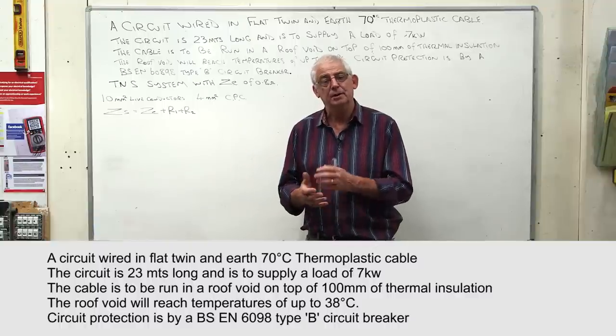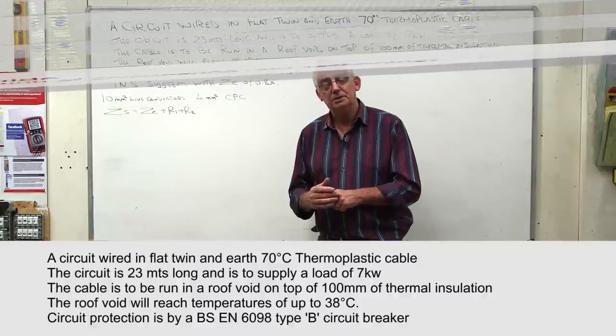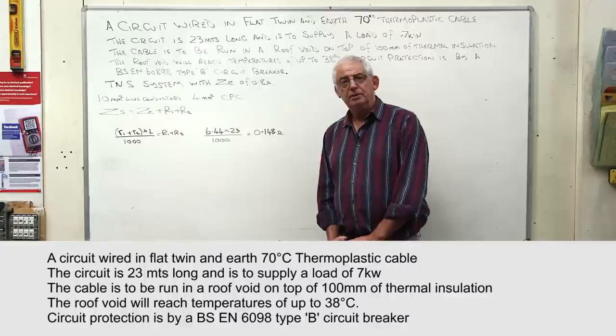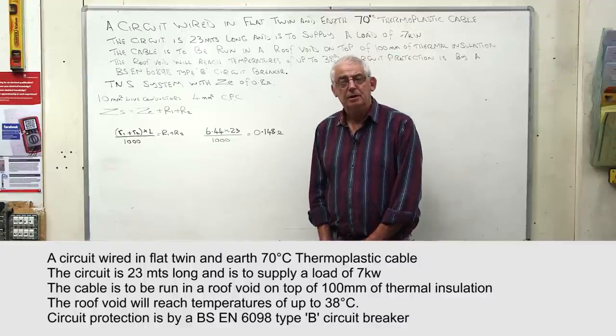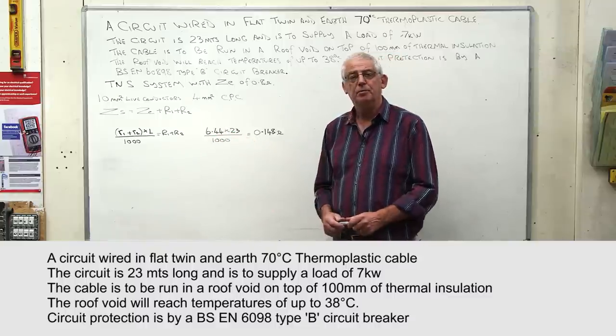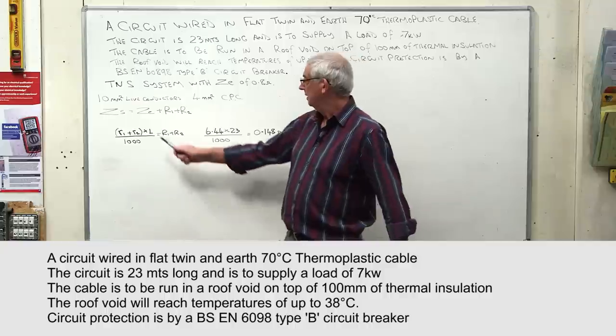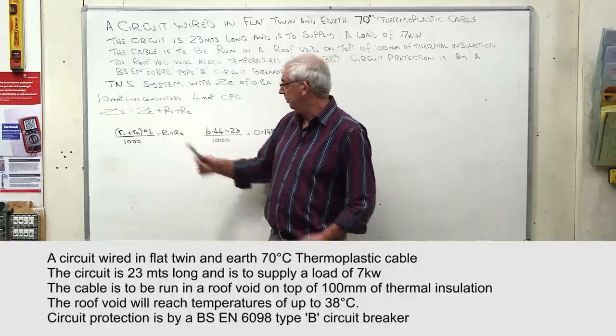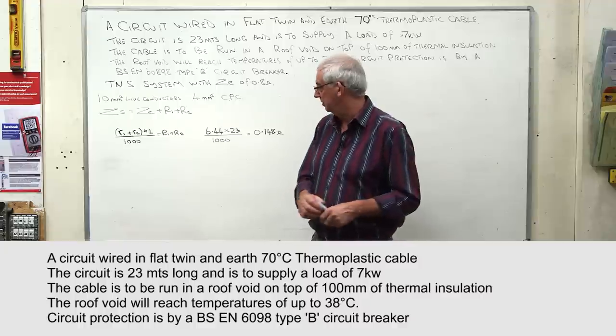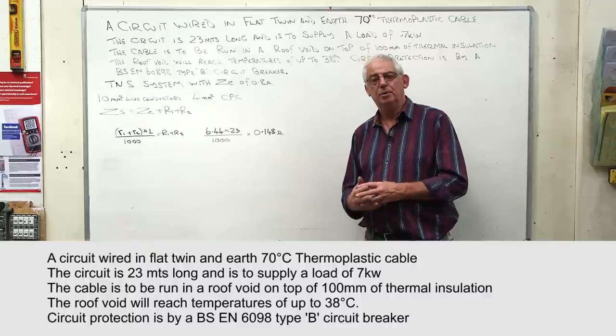Table L1 of the On-Site Guide gives resistance values for cable combinations. For a 10mm² line conductor with a 4mm² CPC, the resistance is 6.44 milliohms per meter. Multiplying that by the cable length of 23 meters and dividing by 1000 gives R1 + R2 for the full cable length — referred to as big R1 + R2 — which calculates to 0.148 ohms.